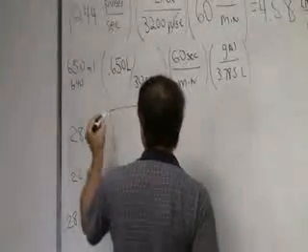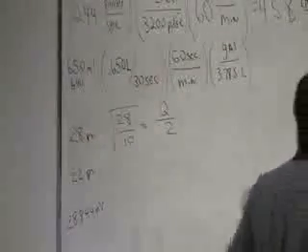So I'm going to try to figure out what, at 28 psi, the flow should be based on nozzle specifications. I used the orifice equation: the square root of 28 over 10 is equal to Q over 0.2 gallon per minute. You can see that. Hopefully I was going to move over to the middle at some point, but started way too far. And when I do that, I get a value of, and I'm going to put it way over here, 0.335 gallons per minute. Something like that.